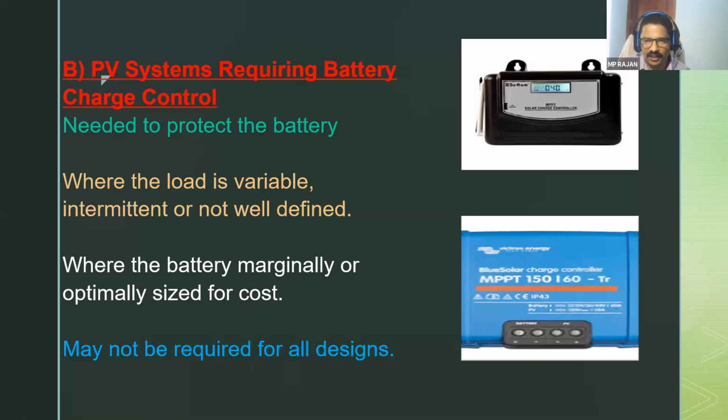When the discharging is going, DOD, beyond DOD we have discussed last class, the maximum depth of discharge we can go, that is DOD. If you go beyond that, it will cause sulfation-like problems, and the life of the battery will be reduced. So battery protection is required. Your charge controller is protecting your battery from overcharging and over discharging.